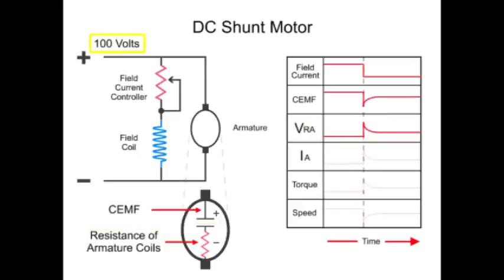Thus, if there is 100 volts applied and the CEMF is 80 volts, the drop across the resistance of the armature coils will be 20 volts.